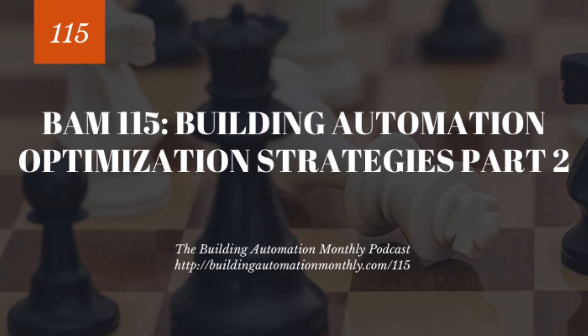All three of those scenarios, you can still throw out bad values by looking at 0 CFM or very low CFM and damper position. This is a real simple AND gate with two comparators. You say, if damper position is greater than a certain percentage and CFM is below a certain value, then say that the box has failed and throw that value out.